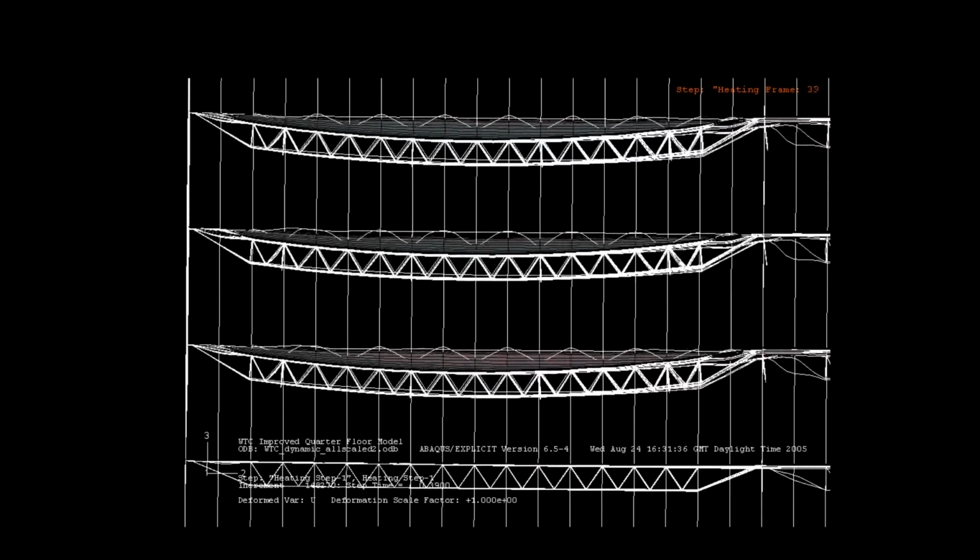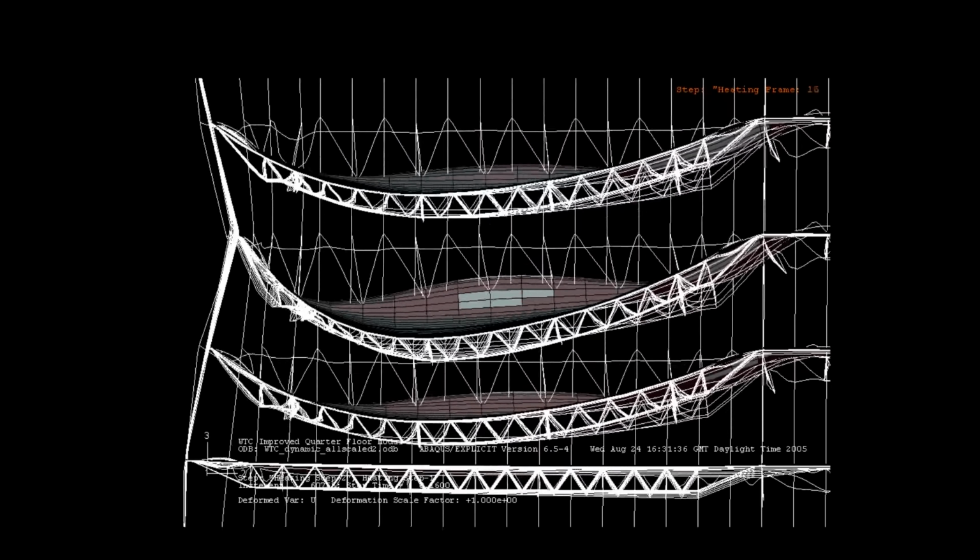Despite the natural redundancy available, it is important to account for the effect of thermal deformations and alternative load paths during the design phase. If we design structures neglecting these effects, we could potentially compromise safety by unwittingly enabling collapse mechanisms specific to fire. This is even more likely if we do not consider realistic fire scenarios and exclusively depend upon prescriptive rules. This approach wastes fire protection through indiscriminate application. Worse still, it may not provide sufficient protection where greater protection may in fact be required.